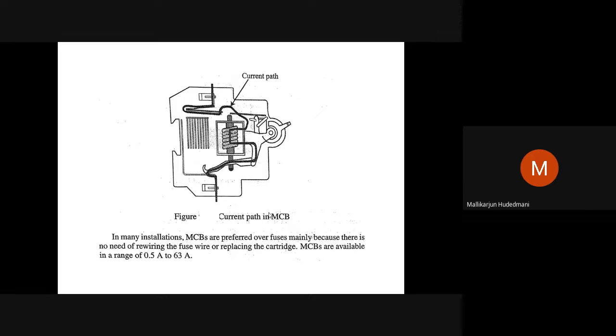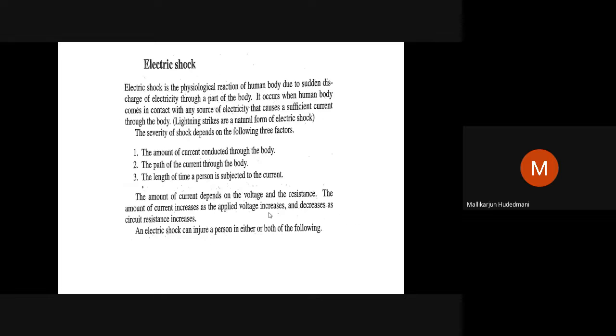In this way, we have single pole, two pole, multi-pole at higher ratings available, from minor rating to very large rating. You can imagine an industry, a person in contact with the power supply, if this kind of circuit breaker is there to trip on occurrence of a certain high draw of current, definitely it saves the life. Otherwise, the person who got in contact with the live wire would have lost his life itself. So in such areas, this safety aspect is going to help. Okay, this was about the MCB.